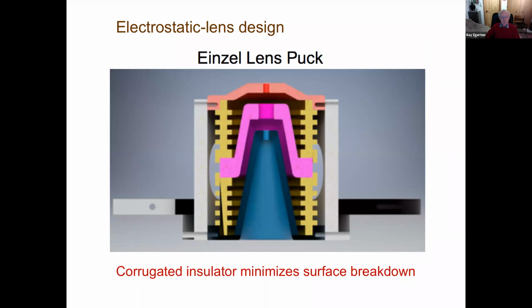Now, an electrostatic lens is basically simple, has 3 electrodes. The pink electrode here is the one to which a negative voltage is applied. And it's supported by an insulator, which is the yellow structure. And you'll notice that it's corrugated, because the main problem with electrostatic lenses is breakdown, electrical breakdown within the lens. And that breakdown usually occurs as surface breakdown. And that process can be avoided or hindered by making the surface area as large as possible, the path between the negative voltage and the ground as large as possible. And so the insulator here is corrugated for the same reason that electrical pylons have their insulators corrugated.